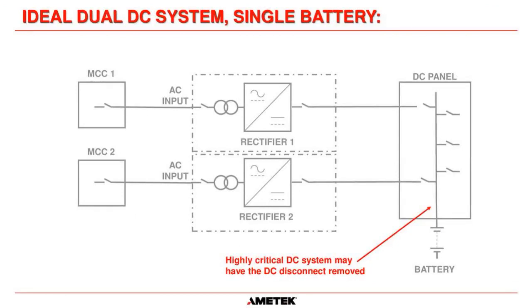And the only difference on this slide is that for some systems, usually for DC lube oil pump systems, where it is absolutely critical that the DC lube oil pumps run when the turbine needs to cool down, and we need to keep lube oil going to the bearings. So in those systems, they won't have a disconnect and they won't have an overcurrent device, because they want to make sure that the battery feeds the DC lube oil pumps at all times when the power is lost. So in some highly critical systems, you may see that the battery is just connected directly onto the DC bus without a disconnect.